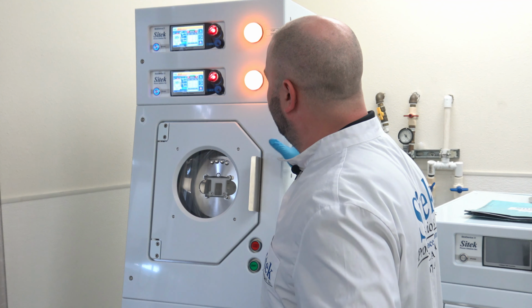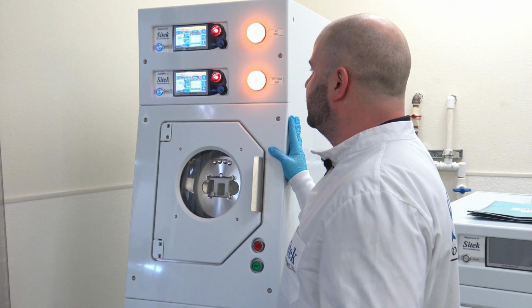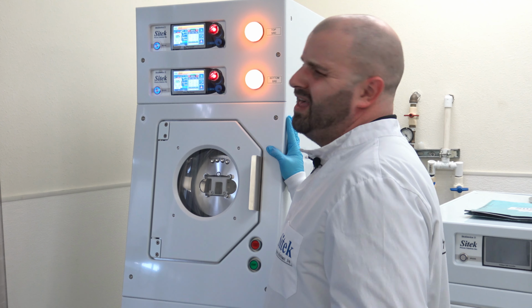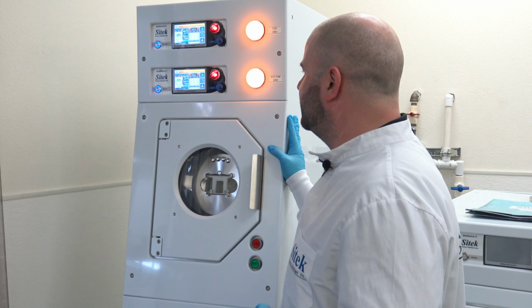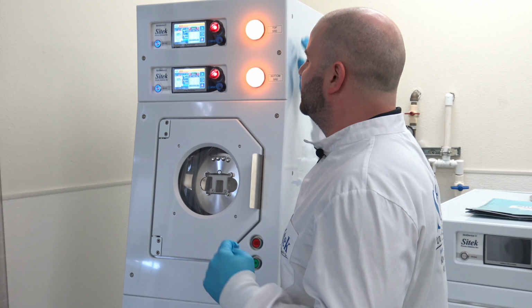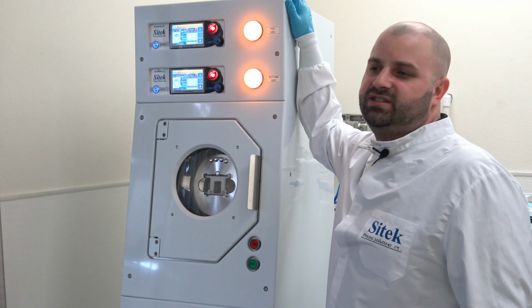They're going to run a 60-second rinse at 500 RPMs before we speed up for a 10-second purge at 1800 RPMs. We maintain this speed for an additional 90 seconds, and then we slow it down to 500 RPMs again for an additional 320 seconds in our dry 2.